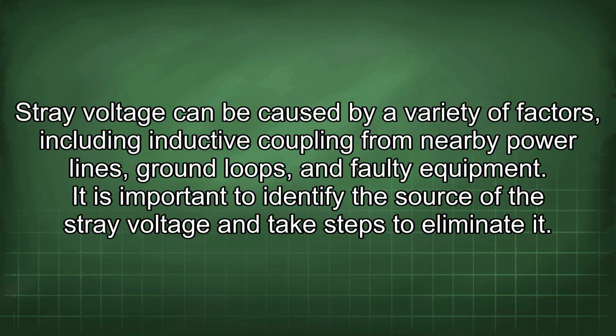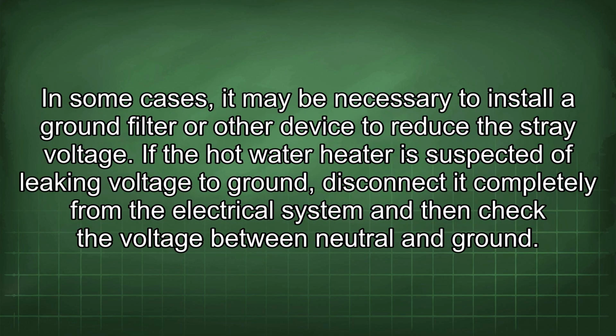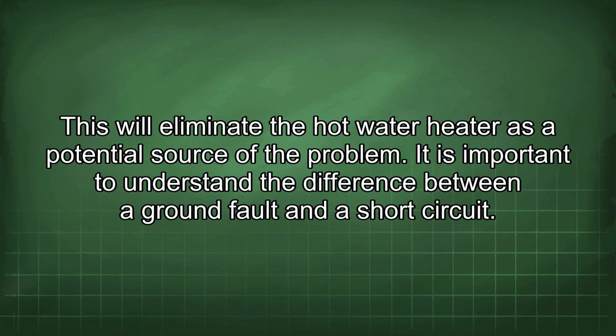Stray voltage can be caused by a variety of factors, including inductive coupling from nearby power lines, ground loops, and faulty equipment. It is important to identify the source of the stray voltage and take steps to eliminate it. In some cases, it may be necessary to install a ground filter or other device to reduce the stray voltage. If the hot water heater is suspected of leaking voltage to ground, disconnect it completely from the electrical system and then check the voltage between neutral and ground.